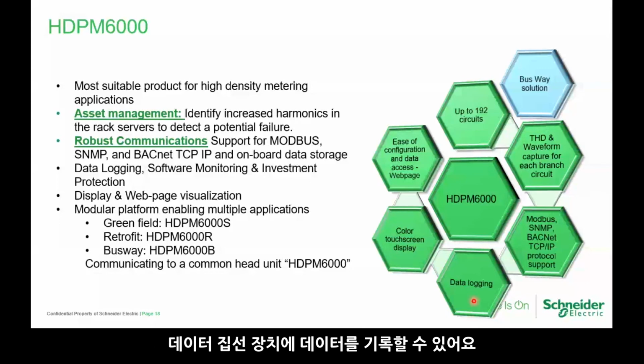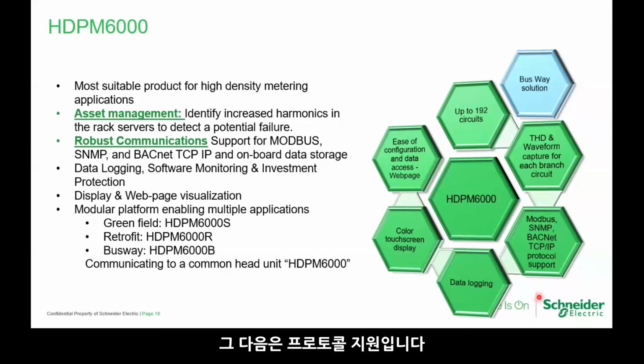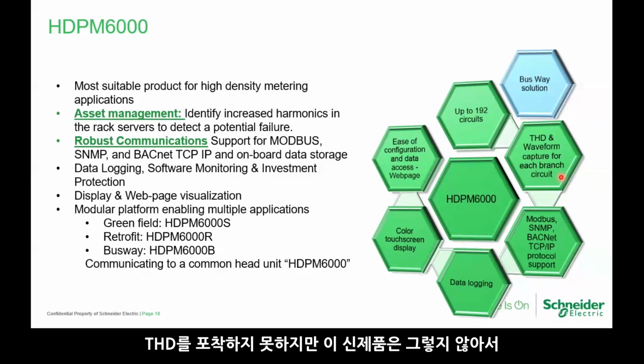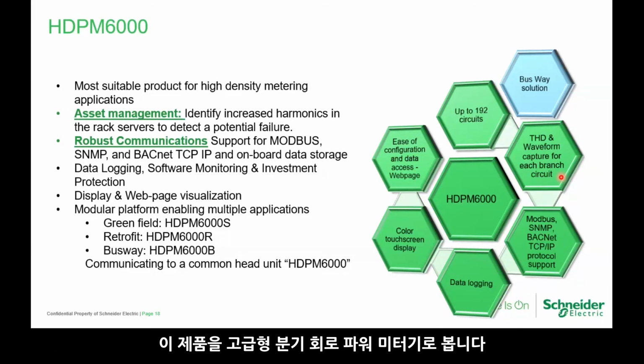This new offer has data logging capabilities, so you can log data into the data concentrator. You won't lose any information if there's a communication breakdown between the hardware and the software. It also supports several protocols besides Modbus RTU - also BACnet and Modbus TCP. And most importantly, it has total harmonic distortion and waveform capture for each branch circuit, which our existing BCPM doesn't really have at every circuit. So we are positioning this as an advanced branch circuit power meter.